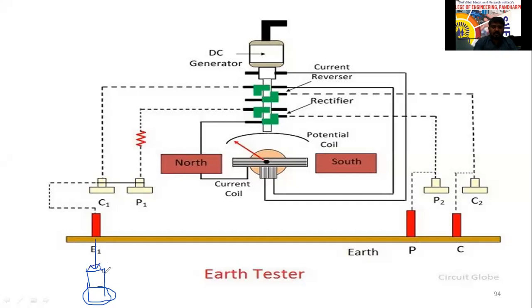Here the earthing electrode is there. That one is connected to these two, P1 and C1, which are shorted here now and connected to this auxiliary electrode. We are going to call this the auxiliary electrode, which is connected to the earth pit.